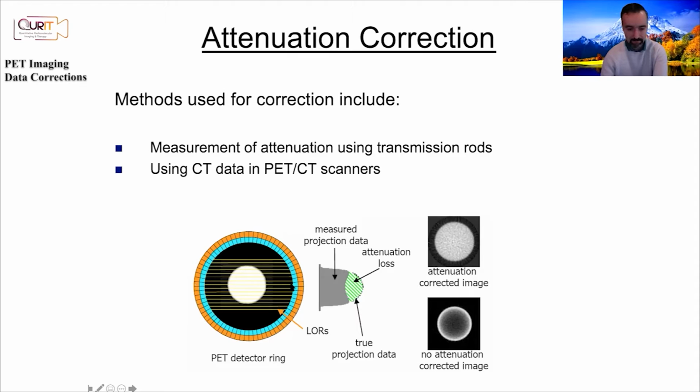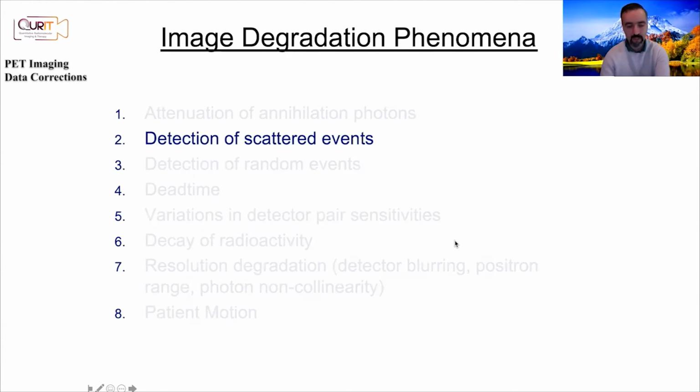So if you're projecting, let's say, along this circle here, you're supposed to get a profile like this. This is just a projection because there's more stuff happening here, more signal along this than there. You're supposed to get something like this, but in practice, you will get something like this because a lot of events are being lost here, attenuated here, but you can correct for that. You can figure that out using the attenuation map. And so you go from an image here where there's a big dip to a nicely reconstructed image that would be flat. Okay, so that's the discussion of attenuation.